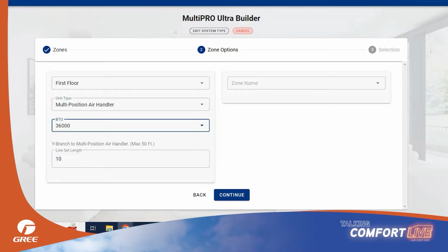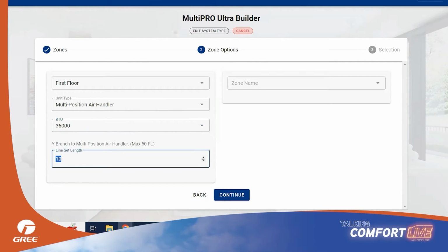handler. In this case, in this first floor, we know that we need a 3-ton unit, for example. So we're going to select 36,000 BTUs. Next, we'll have the distance from the Y branch to the multi-position air handler. In this case, it says it's maximum of 50 feet. We know that we need about 20 feet from the Y branch to that air handler. So we enter 20 feet. Now we do our other zone.